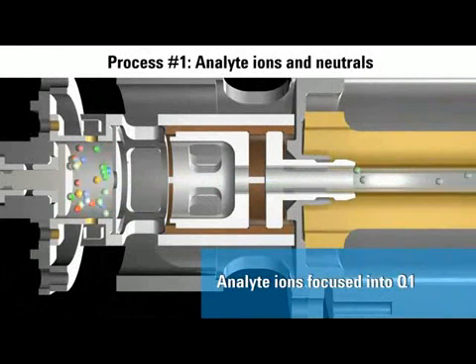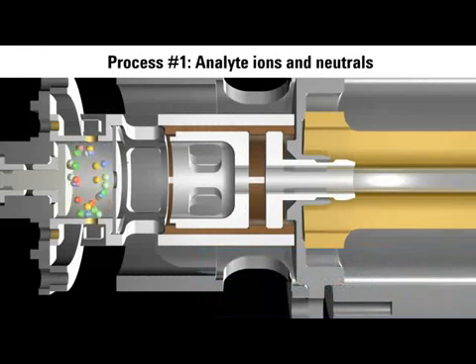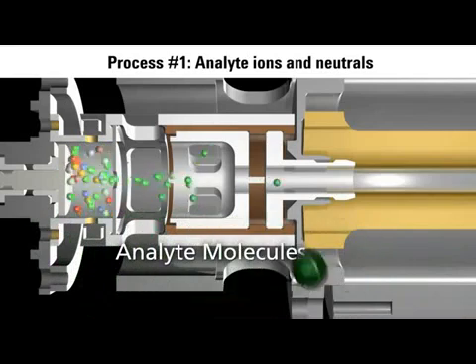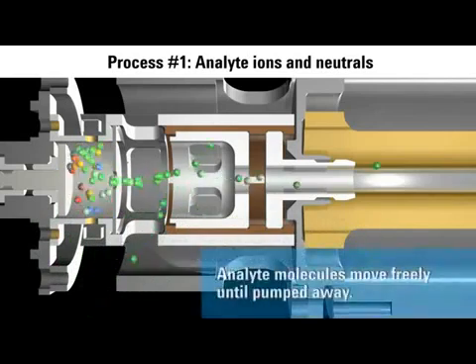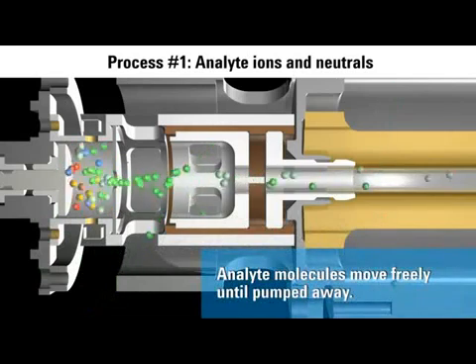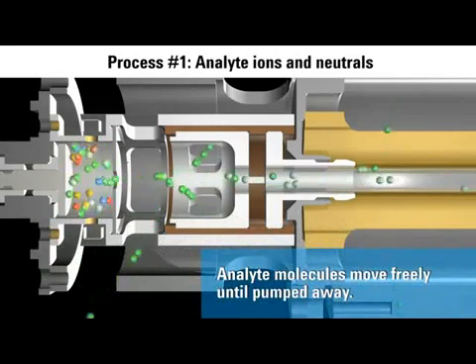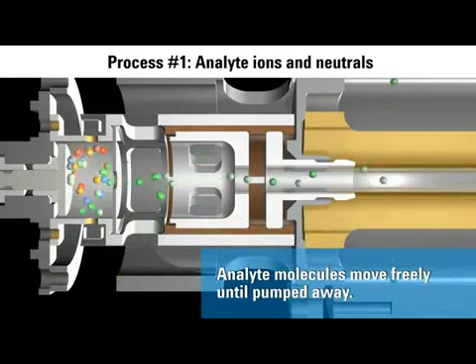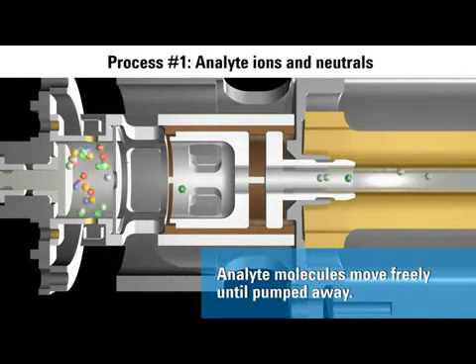Analyte ions are immediately extracted from the source and focused into the quadrupole mass filter. But what about the non-ionized molecules? The electrical fields within the MS have no influence on these molecules — they follow rapid random motion until removed by the vacuum pump.